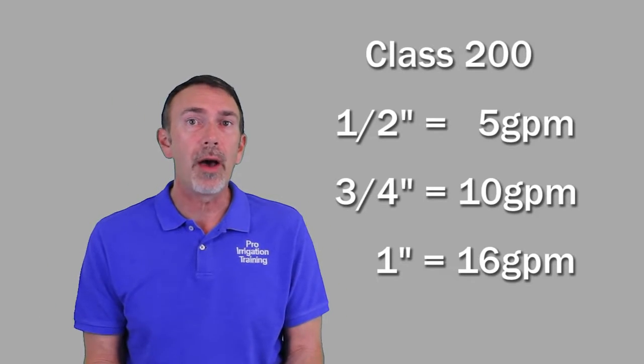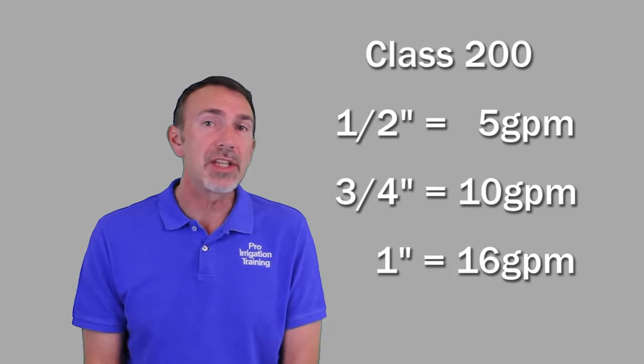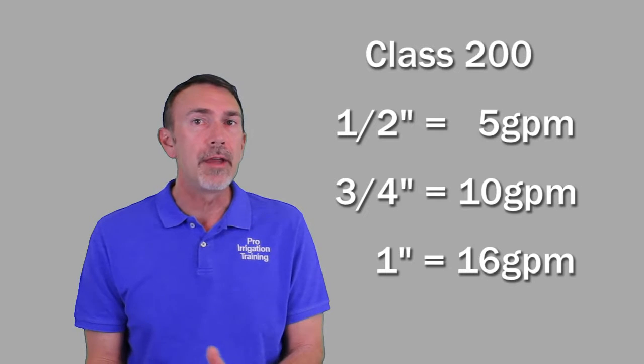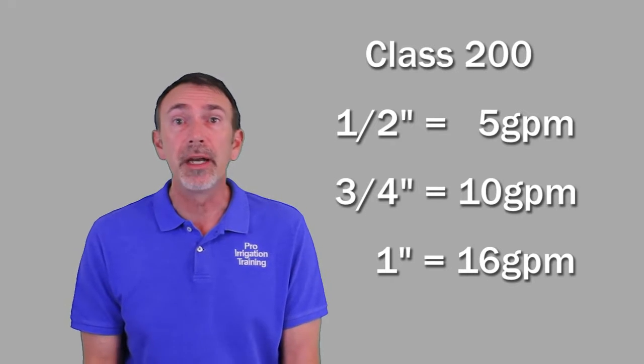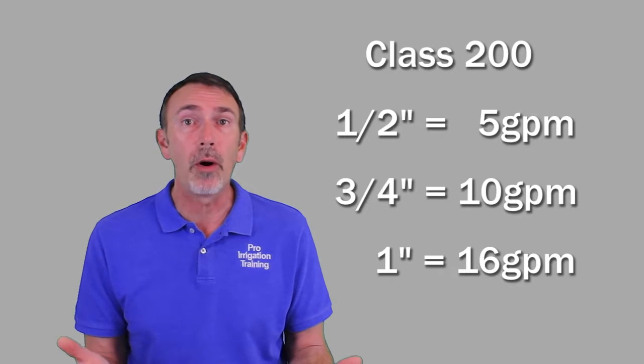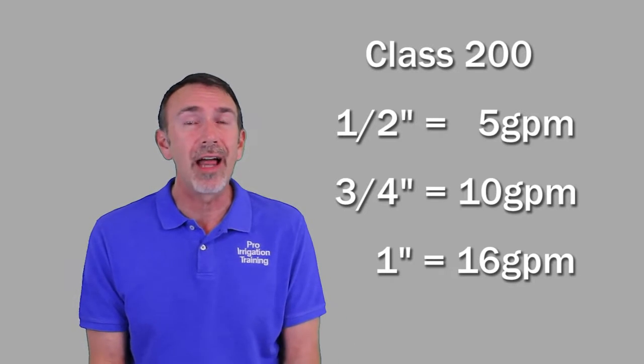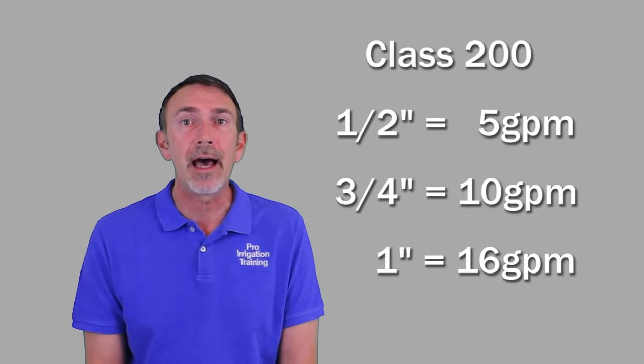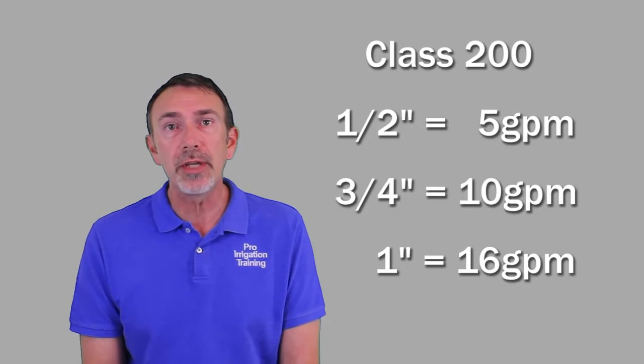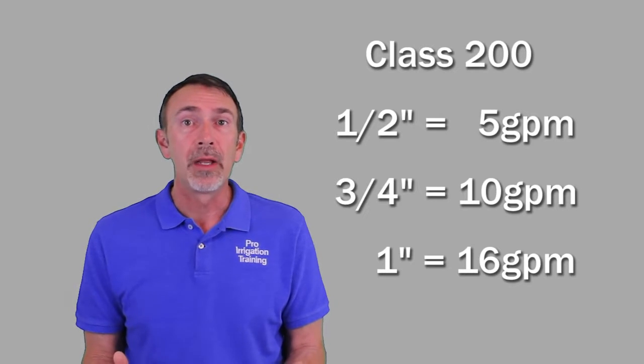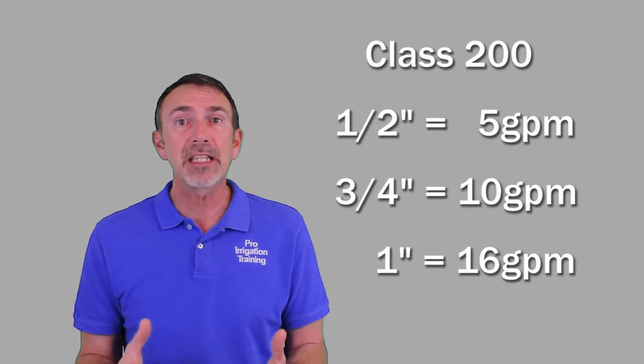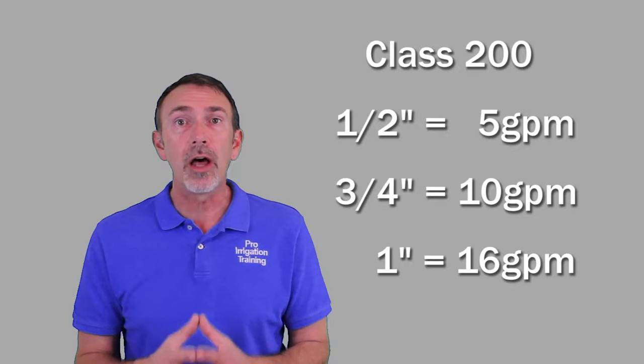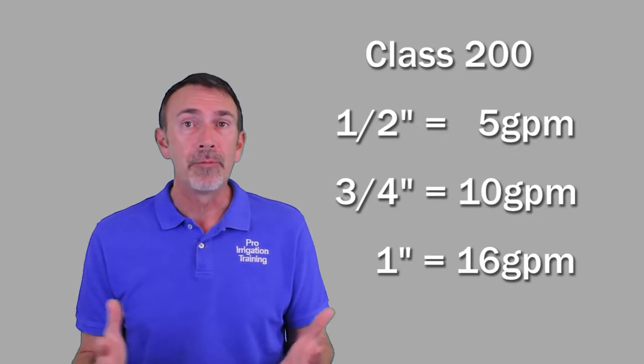So let's go through our fill in the blanks and talk about what the maximum flow rate is. On the Class 200 pipe, a half inch piece of pipe will actually be Class 315—it has a 315 PSI maximum operating range. And what you get for that is five gallons per minute. You can get more than that, but that's the maximum rating at the speed, the velocity at which we want water to stay at with PVC pipe.